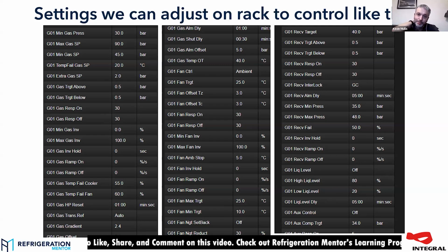The setting I just wanted to point out with boosting the receiver pressure, in the last column there, is receiver interlock. Receiver interlock watches the minimum pressure and the maximum pressure for the receiver, and it will allow the high pressure valve to either shut if the receiver gets too high, or open if the receiver pressure gets too low. And that's really useful because in low load conditions it's easy for the receiver pressure to get too low if you haven't got a gas bypass.